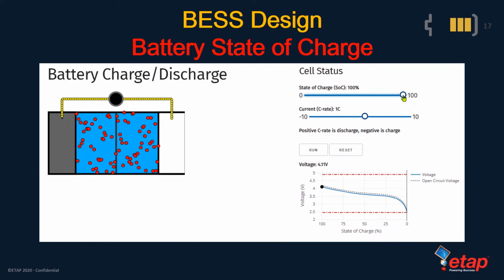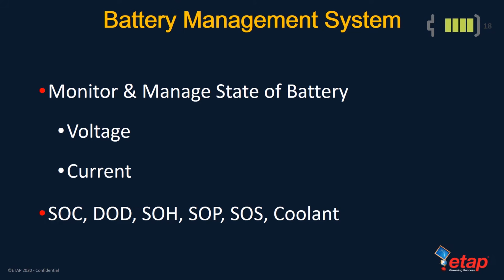Another way of looking at C rate is through an example. When a 100 kilowatt-hour battery in a Tesla Model S P100D electric vehicle is undergoing supercharging at 120 kilowatt, the C rate is 1.2 per hour. And when that battery delivers its maximum power of 451 kilowatt, its C rate is 4.51 per hour. So we see that the battery management system gives us the ability to monitor state of charge. But the BMS is more than that.